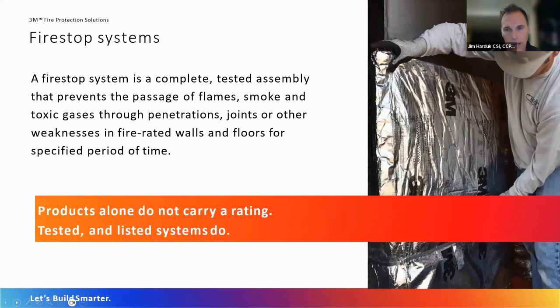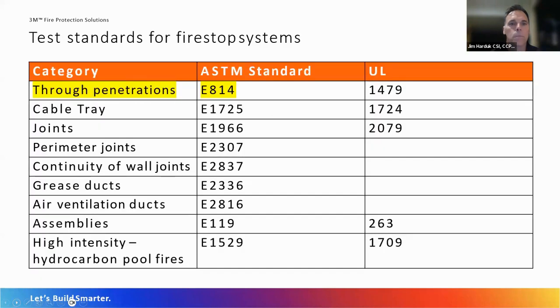And the most important thing I want you to take away from this slide is that these Firestop products that I'm going to talk about later in the presentation, those products by themselves do not carry any rating. They become rated when they're used as part of a tested system or a tested assembly. Next slide. The tested assemblies or systems that I'm going to talk about are all tested in conformance with an ASTM test standard, and that is ASTM E814. Next slide.